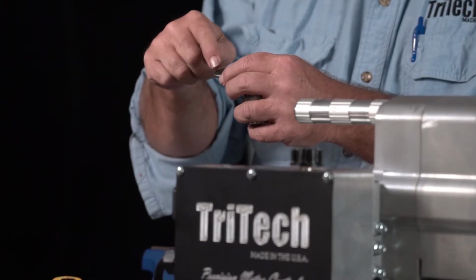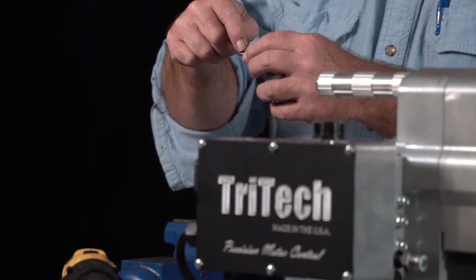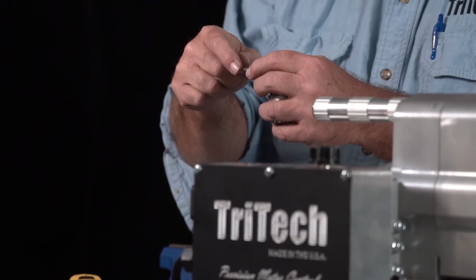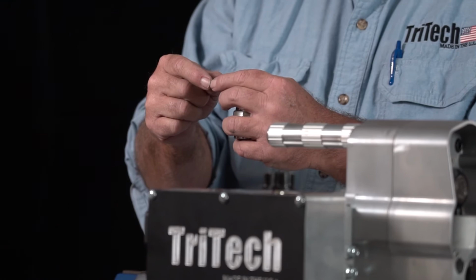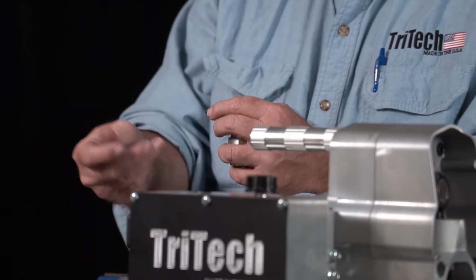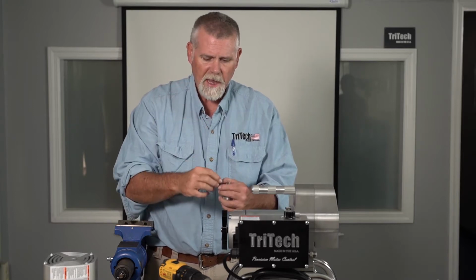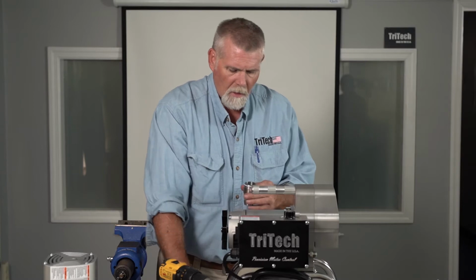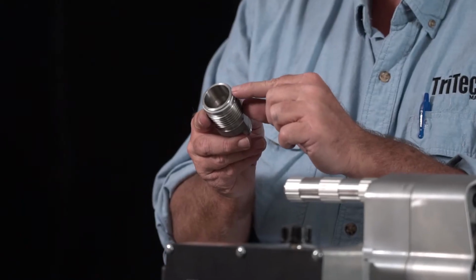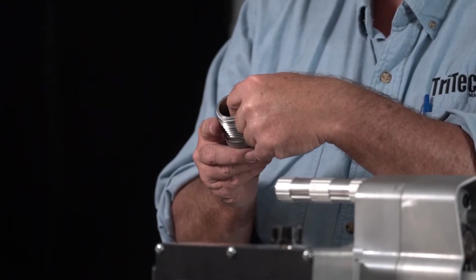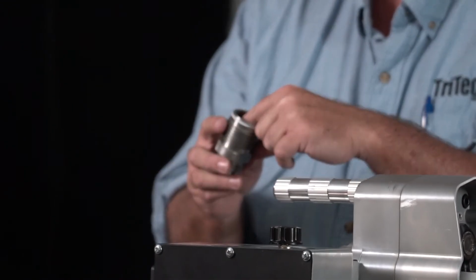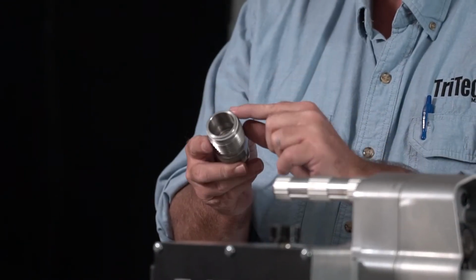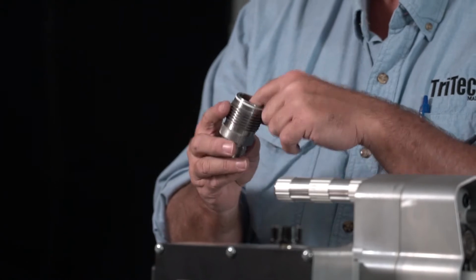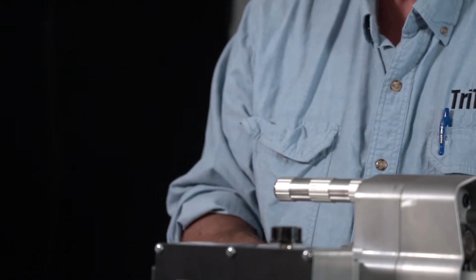Your inlet seat, you want to look at the beveled edge to make sure everything is uniform and there's no chips or imperfections. You get a new ball in your repair kit, but while you're trying to figure out what your problem is, you want to examine that. The O-ring that is on the outside and on the bottom of your foot valve housing, if they're in good condition, you don't need to replace them. If they're damaged or worn, then you replace them. They're in the repair kit.